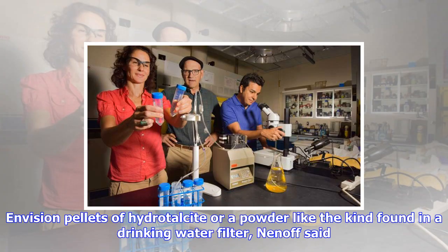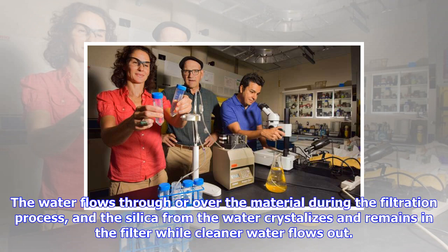As documented in a recent article in the Journal of Water Process Engineering, they found hydrotalcite could remove about 90% of accumulated silica in recycled water and be reused for 5 or more cycles. This ability to reuse the filter and recycle the cooling tower water could save both money and natural resources.